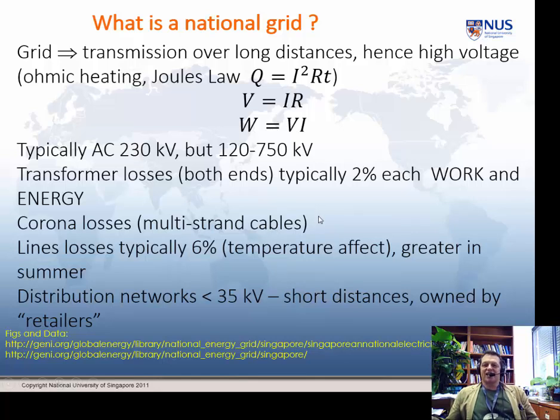The material you make your cables out of is also important, and you have a trade-off here. If you use aluminium, it's very light, but it doesn't have such a good conductivity as something like copper, which is heavier. So to carry the same amount of power, aluminium cables have to be thicker, which of course increases the weight. Typically, line losses, if you want an average number, for a temperate climate, 6%. In summer or Singapore, you might be looking at 8% because of the increased resistance.